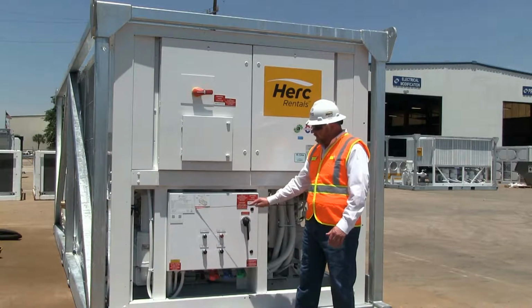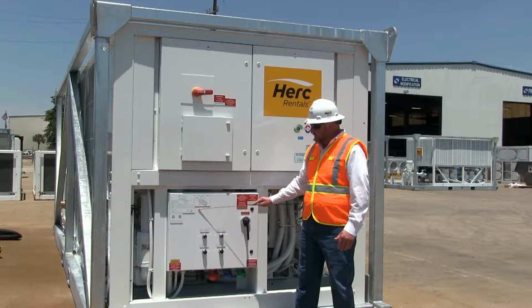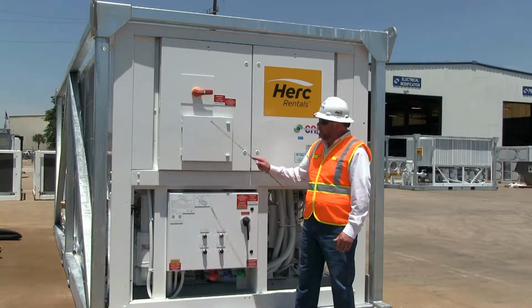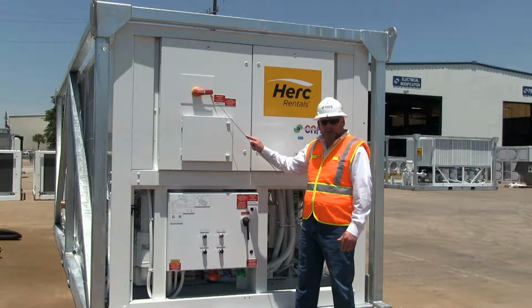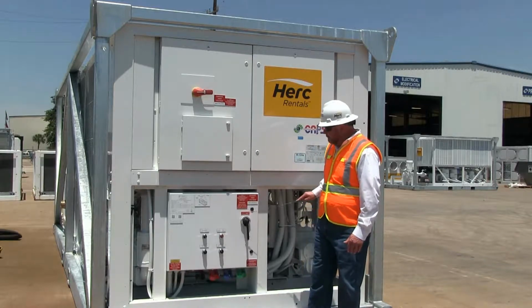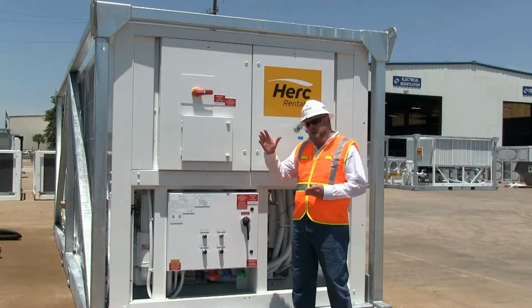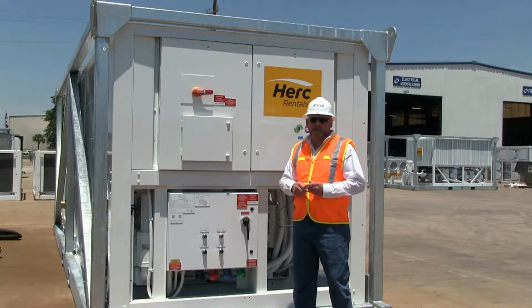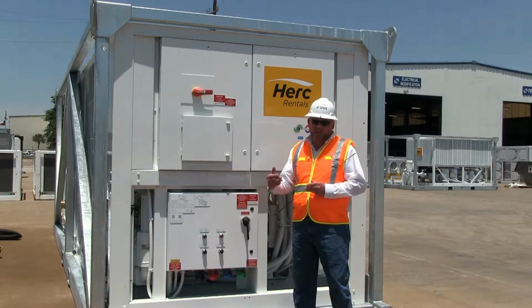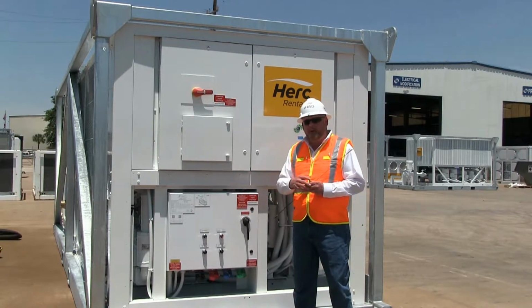We also have clearly identified a lifting diagram here beside the panel, and both the main chiller and the pump have an integrated circuit breaker. So all of our internal electrical components of the machine are protected by high voltage line sized breakers. You'll only have to protect the cable coming to the machine either from a generator or from the permanent power source.